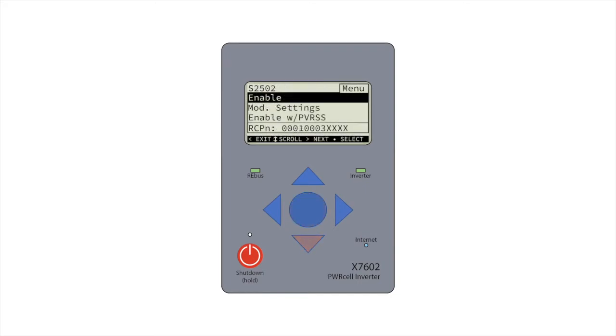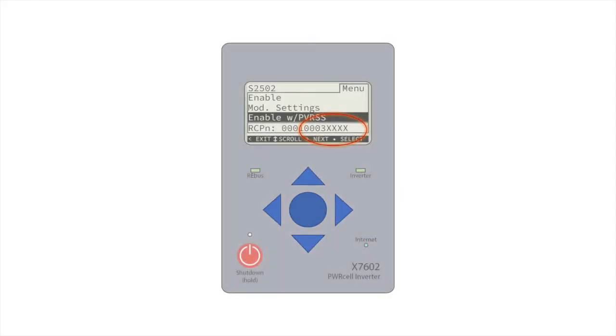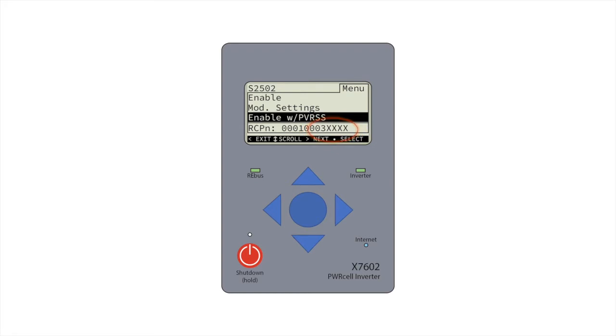In each device menu page, make note of the RCP number, or RCPN. We can record the unique last five digits for each device. This is especially helpful for the PV links to confirm they match with the values collected from the array sitemap.